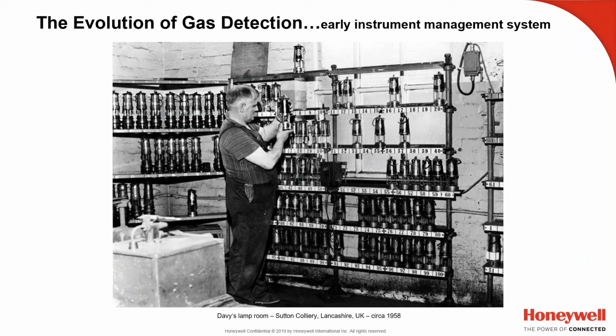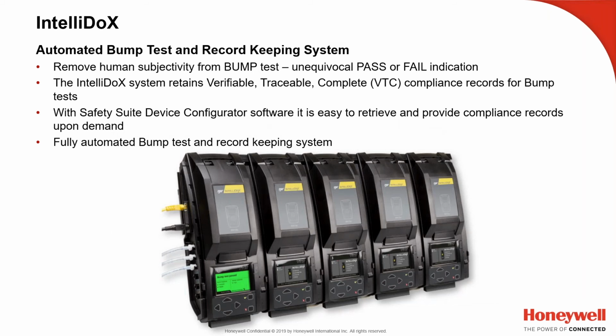So talking about these instrument management systems, this is the picture I was referring to over in the UK. In 1958, they were very diligent about maintaining their instruments, but it was probably just stickers and paperwork that they did with pen and paper. Now it can all be done automatically, bump test and record storage system with the IntelliDoX, BW IntelliDoX. It removes or mitigates human subjectivity from bump test, and it gives you unequivocal pass and fail indications. Like the screen, it's simply green, yellow, and red.